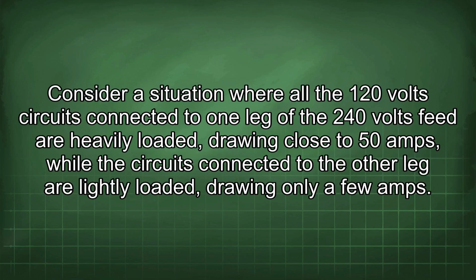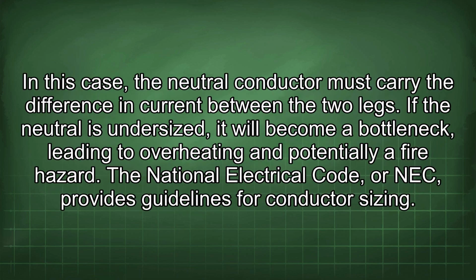Consider a situation where all the 120-volt circuits connected to one leg of the 240 volts feed are heavily loaded, drawing close to 50 amps, while the circuits connected to the other leg are lightly loaded, drawing only a few amps. In this case, the neutral conductor must carry the difference in current between the two legs. If the neutral is undersized, it will become a bottleneck, leading to overheating and potentially a fire hazard.